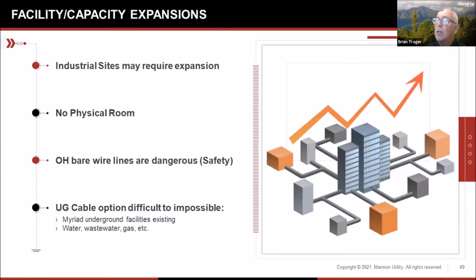Then we have what we call facility or capacity expansions. Industrial sites don't seem to have a whole lot of extra space on site. So those sites may require expansion if the business is expanding itself, or may require more capacity for bigger motors. There's really no physical room. Overhead bare wire lines are dangerous. They're always a safety issue, whether it's pulp and paper or storage or what have you. And the underground cable option may be difficult. It may be impossible. There's a myriad of existing underground facilities: cables, pipes, water, gas, wastewater, et cetera, et cetera.